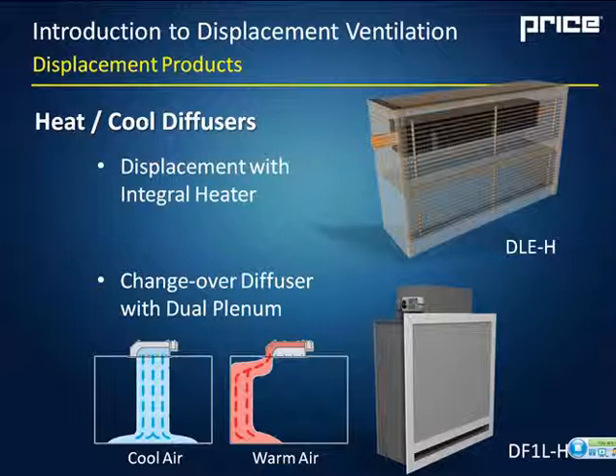We also have the changeover diffusers, which we've done a lot of development on in the last couple of years. You can see the depiction of the pattern here, where you have the larger perforated face active in the displacement mode or in the cooling mode. So the cool air just spills out of that diffuser. This diffuser is mounted in the ceiling. It's going to spill out of the diffuser and then travel across the floor.